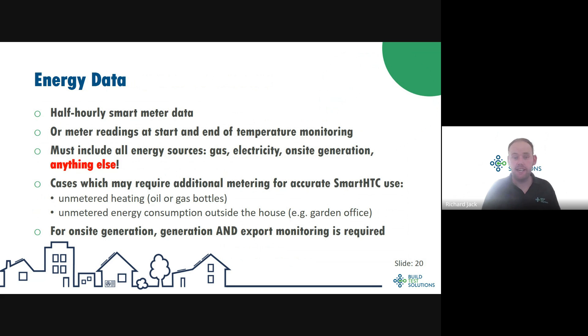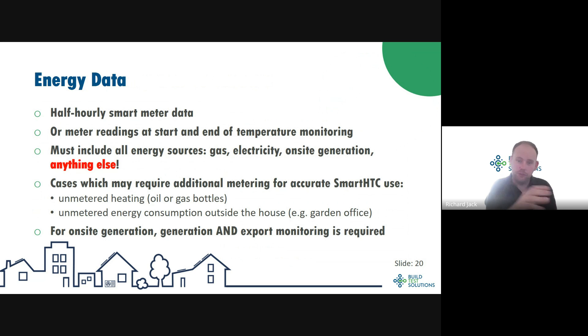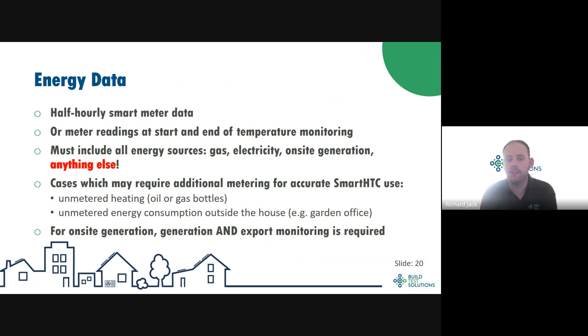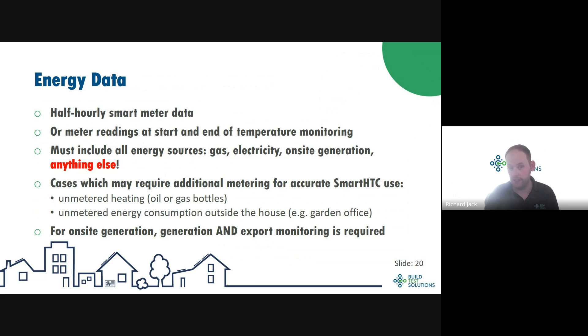For energy data, you can either use half-hourly smart meter data or the total energy consumption over the period from meter readings taken at the start and end of your temperature monitoring. It's totally critical to include all sources of energy use in the building — we're inferring heat loss based on heat input, so if we don't measure those heat inputs we won't get an accurate measurement of the heat loss. Smart HTC is therefore difficult to use in some cases, such as where you have unmetered heating — most commonly oil tanks or gas bottles — or if people are regularly using solid fuel or an open fire during the measurement period.